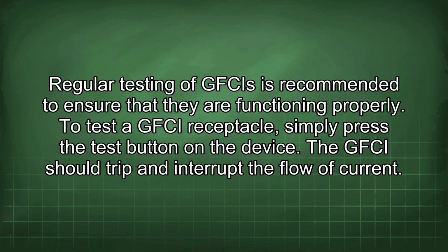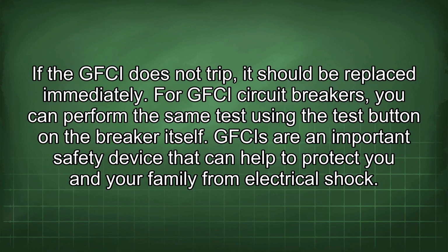Regular testing of GFCIs is recommended to ensure that they are functioning properly. To test a GFCI receptacle, simply press the test button on the device. The GFCI should trip and interrupt the flow of current. If the GFCI does not trip, it should be replaced immediately. For GFCI circuit breakers, you can perform the same test using the test button on the breaker itself. GFCIs are an important safety device that can help to protect you and your family from electrical shock.